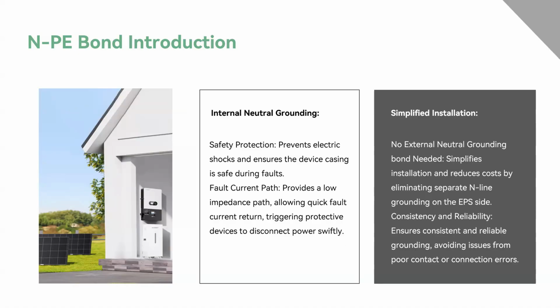For example, it can prevent electric shocks and ensure the device casing is safe during faults, and provide a low impedance path, allowing quick fault current return and triggering protective devices to disconnect power swiftly. Using this function, we can simplify the installation, with no external N-PE bond needed, and reduce the cost by eliminating separate N-line grounding on the EPS side. It also ensures consistent and reliable grounding, avoiding issues from poor contact or connection errors. We can set this N-PE function through our LCD, also through our app and the website.